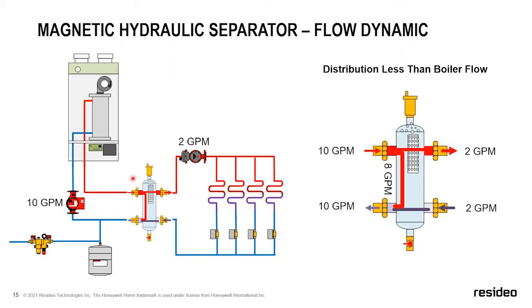What's taking place inside of here is, since there is very little pressure drop, if any, you're creating a spot where the differentials from this circulator are not impacting the pressure differential from this circulator. The same dynamic happens in closely spaced tees if done correctly, and I'll touch on that in a minute. But this basically eliminates any air in the piping, makes it a little bit easier. It also gives you more water volume, so you don't have the displacement as much. So we see this is a very common example with variable speed pumps and valves and or actuators.